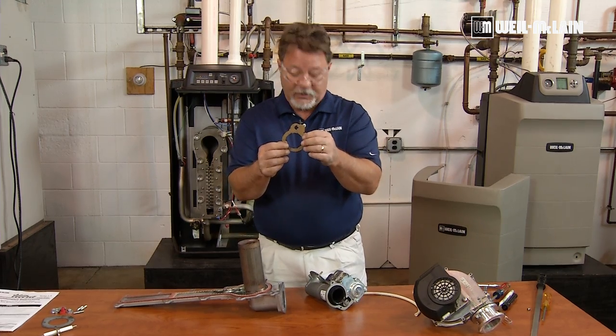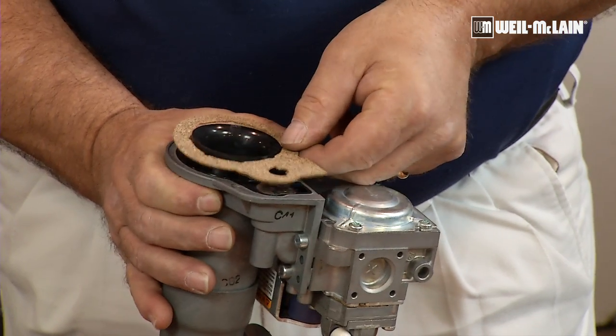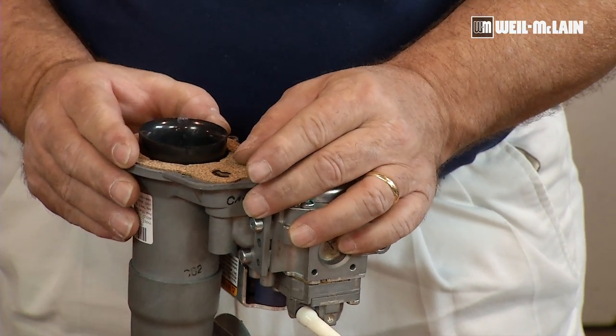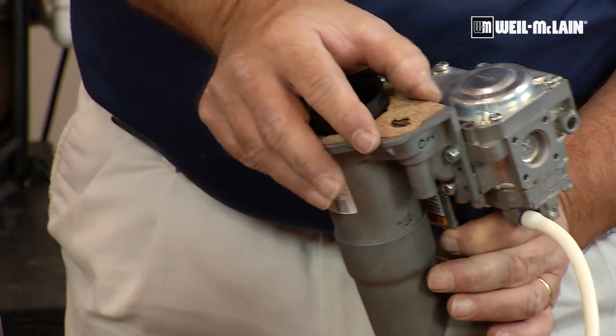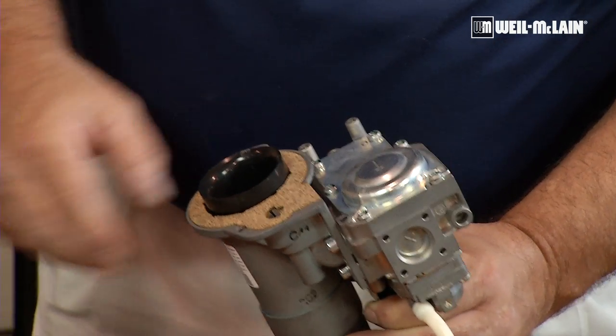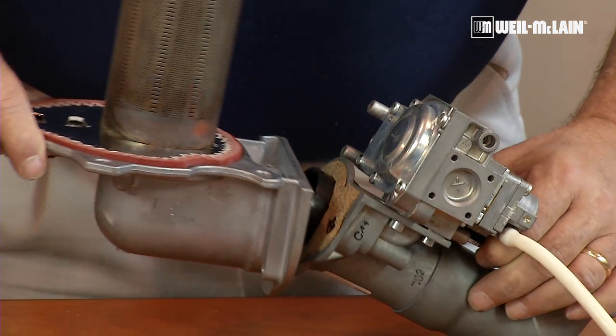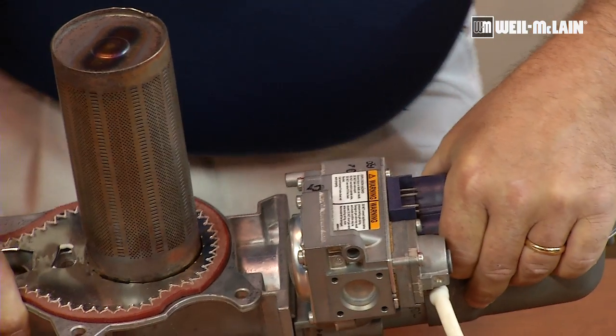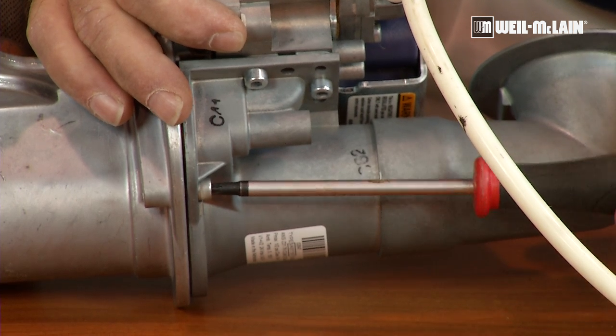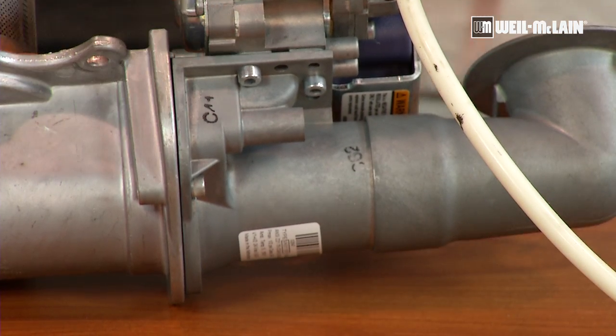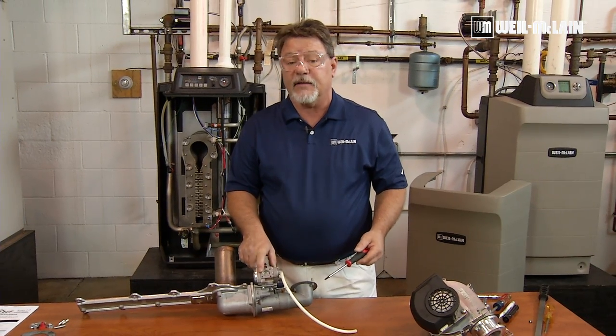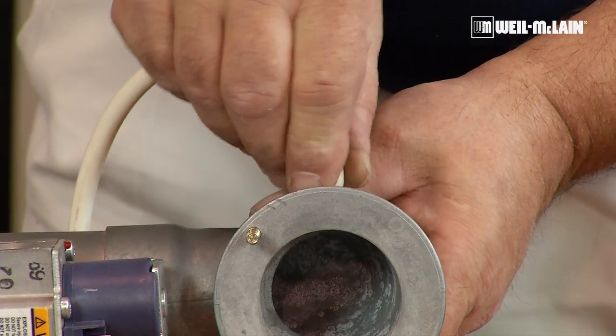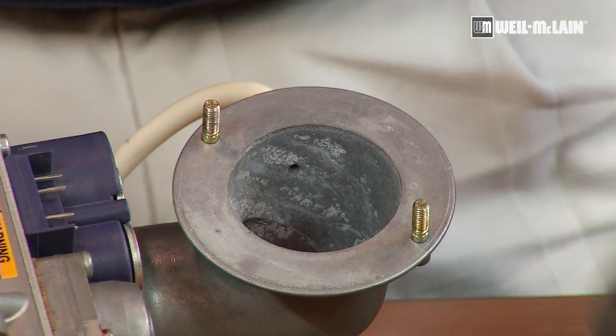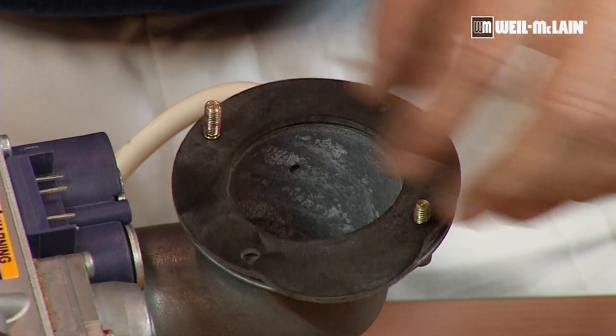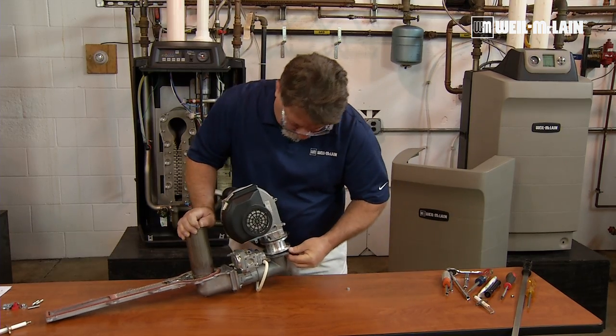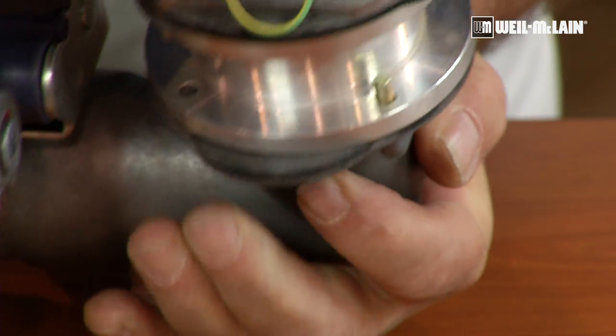So I need to reinstall a brand new cork gasket. I'm going to simply slide that on the venturi, remembering to line up my hole with the mark. Now that they're both snugged up, I do want to make a gas-tight seal on that cork gasket. We're going to reconnect the reference line. New rubber gasket. Now we're going to install the blower and adapter block onto the assembly here.